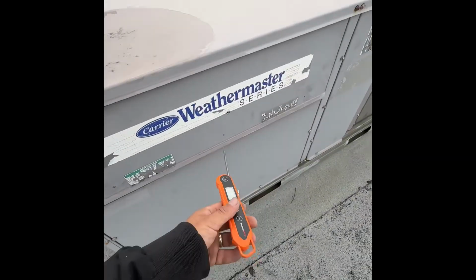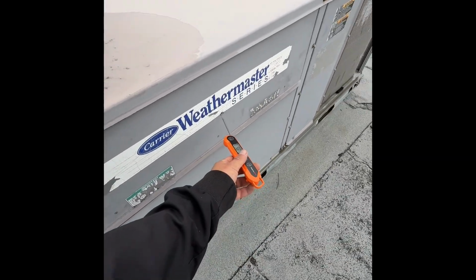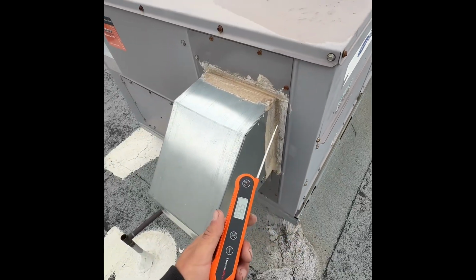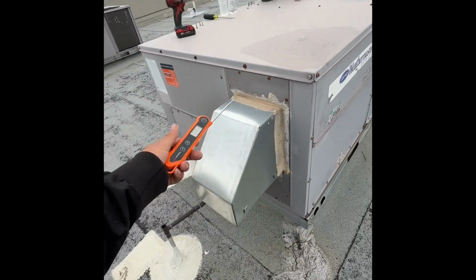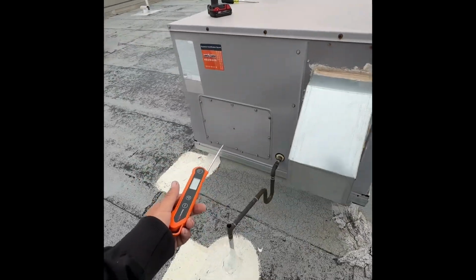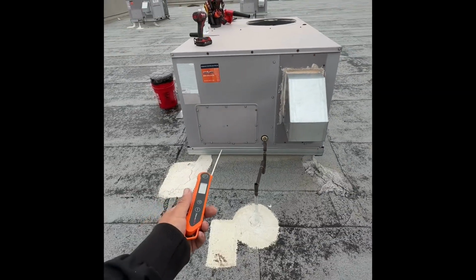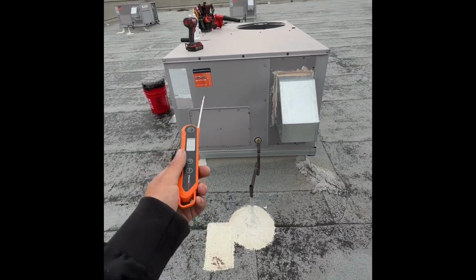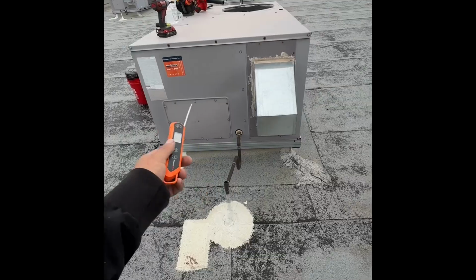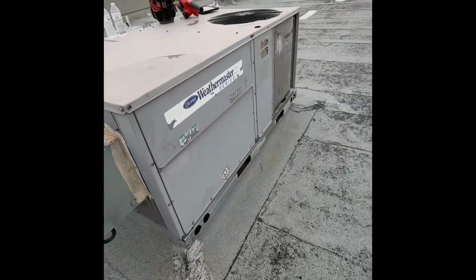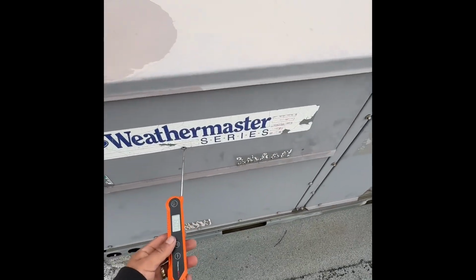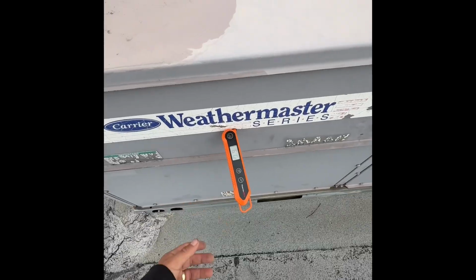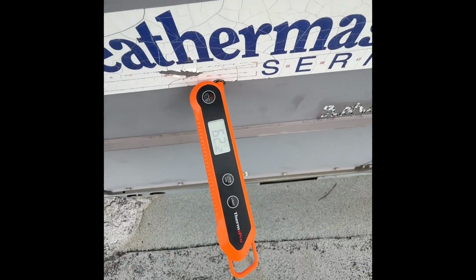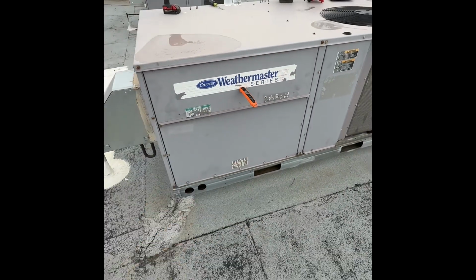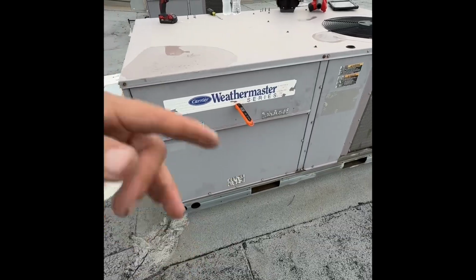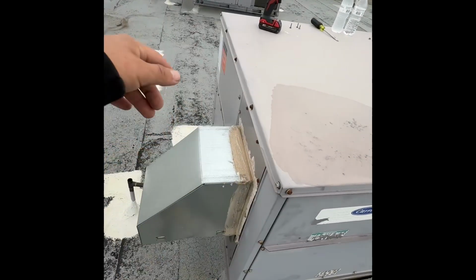Then you go to your return. You could do it where the filters are at in here. There's already a hole there, so I'm using that one. Or you could go through this panel area right here. For package units where it's a side chute, for you new guys, supply, return. Pay attention to the dimensions of the unit, the layout of the unit, and you'll know exactly where to go to look for your readings. So now we're at the return duct. The air getting moved out of the space as opposed to the air going into the space.